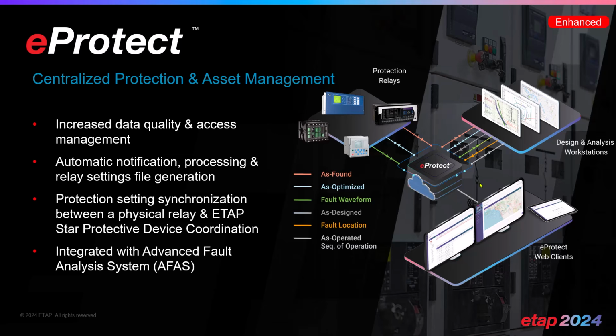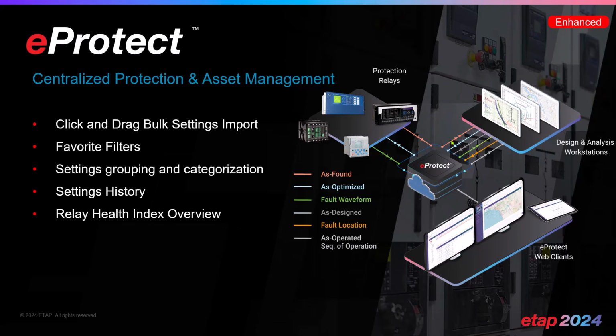This is connected, in terms of protection settings, to ETAP, allowing a bidirectional flow at all times between the relay information, the ETAP model, and the visualization of differences in the configuration files whenever changes are made to relay configurations, giving better protection and handling during commissioning of these systems.